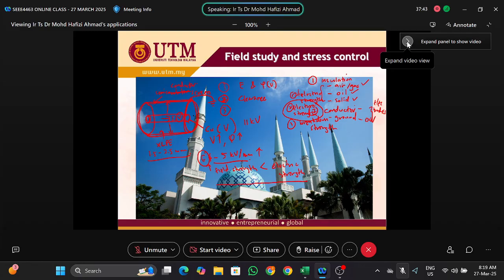So the designer, if you are working for a cable manufacturer, in the case of this cable, you should design your field strength. So field strength depends on the voltage, depends on the configuration or shape, the size of your conductor, the diameter, the radius, everything, the length of this conductor, and also the thickness of the insulation, the inner radius R1 and outer radius R2. So the electric field or field strength is depending on these quantities.